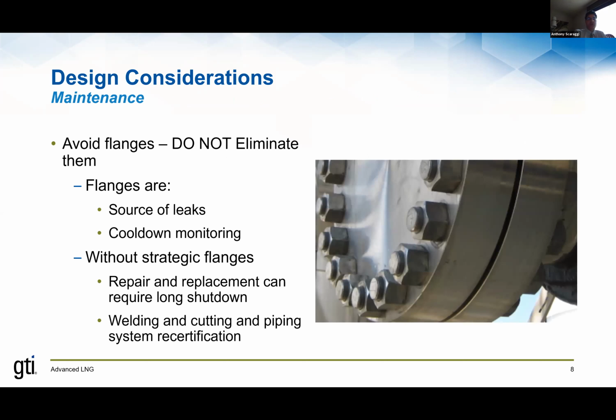One thing that you'll always hear in the LNG industry is that you should avoid flanges on piping systems, and that's excellent advice. Flanges can leak. LNG is very cold. When you first introduce that cold liquid into a piping system, you do it in a very controlled manner, because it will make the pipes contract. The pipes will move as they begin to cool down. Normally, as you can see here on a flange, you've got many bolts. Normally, the bolts will contract at a different rate than the actual steel. So you'll get a situation where you won't have a complete seal on a flange during cool down. And when that happens, you can actually get LNG leaks from the flanges.